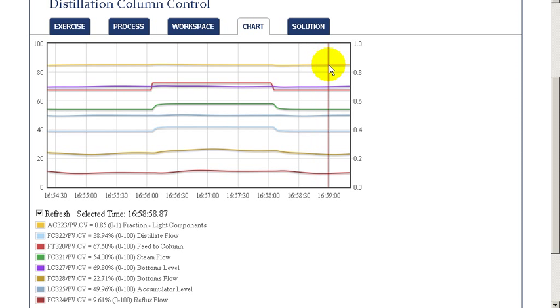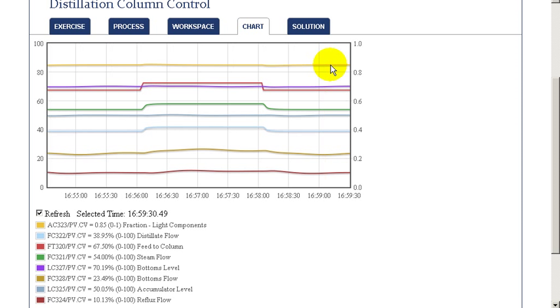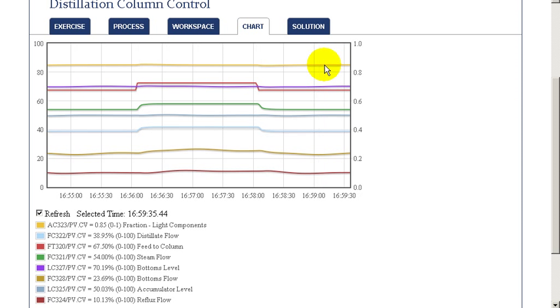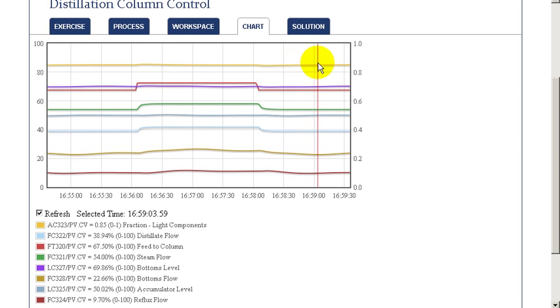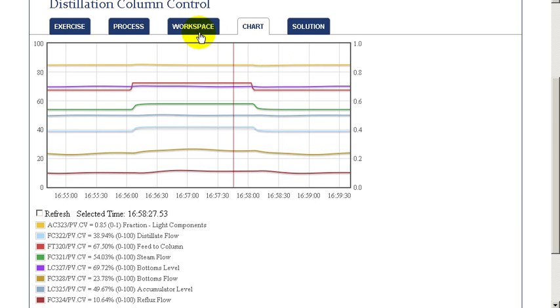As a result, the composition remains very stable even though we've had significant feed rate changes in the column. This really demonstrates the benefit of ratio control on the column and how effective it is in stabilizing the composition.